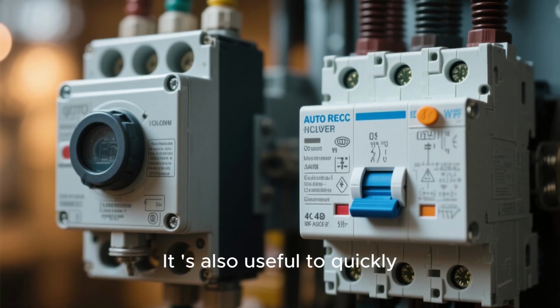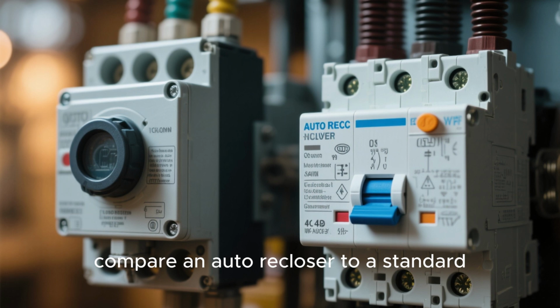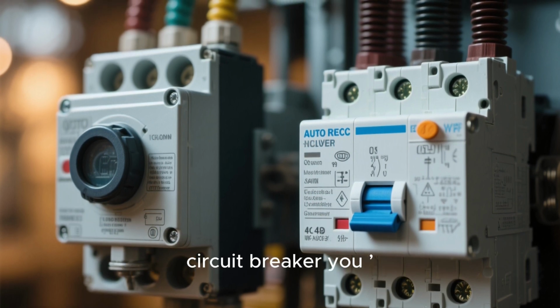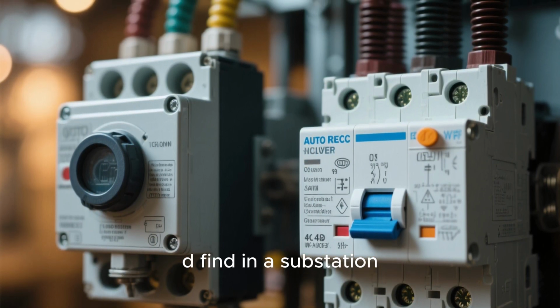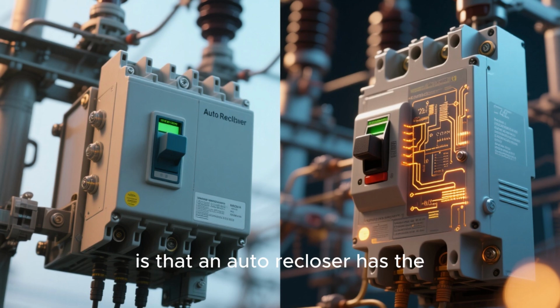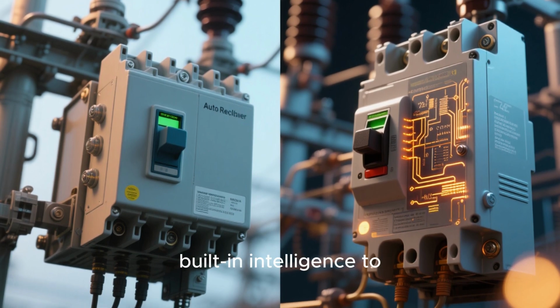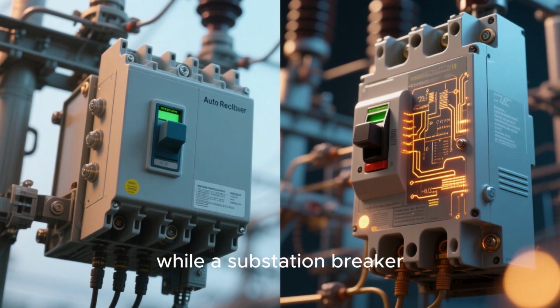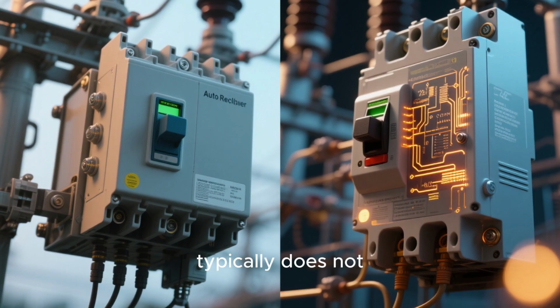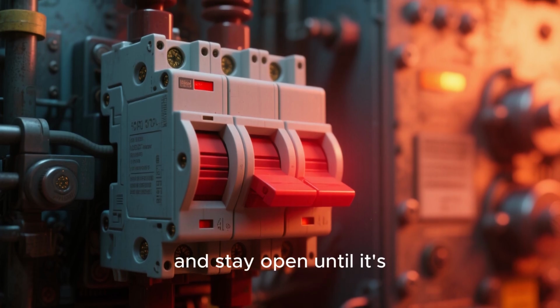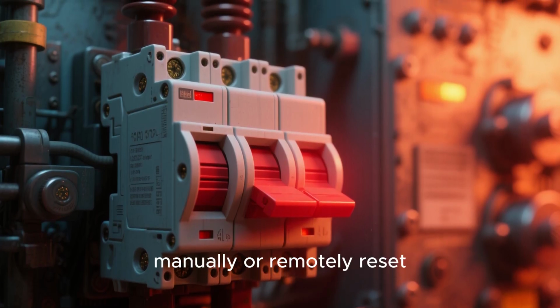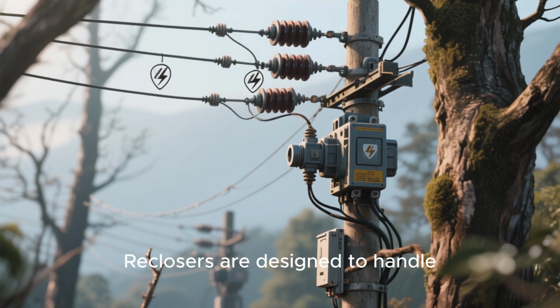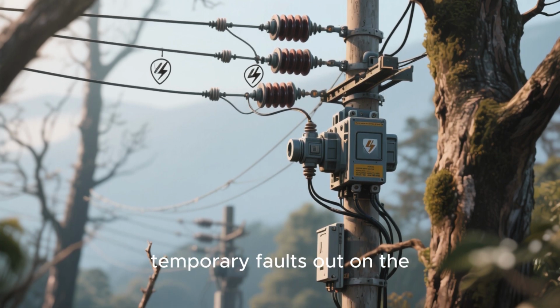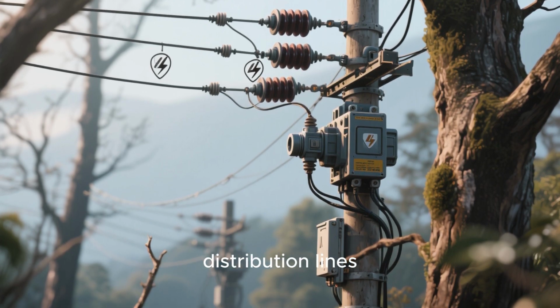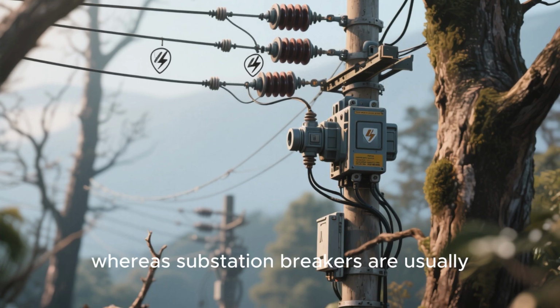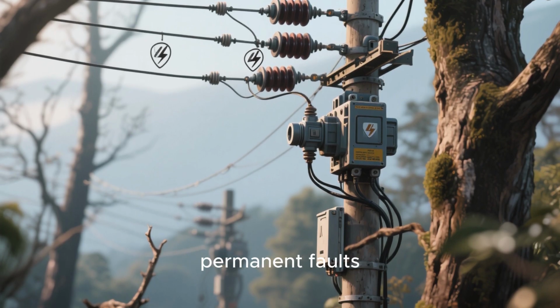It is also useful to quickly compare an auto recloser to a standard circuit breaker in a substation. The key difference is that an auto recloser has the built-in intelligence to automatically reclose, while a substation breaker typically does not. It's designed to trip and stay open until it's manually or remotely reset. Reclosers are designed to handle temporary faults out on the distribution lines, whereas substation breakers are usually the last line of defense for permanent faults.